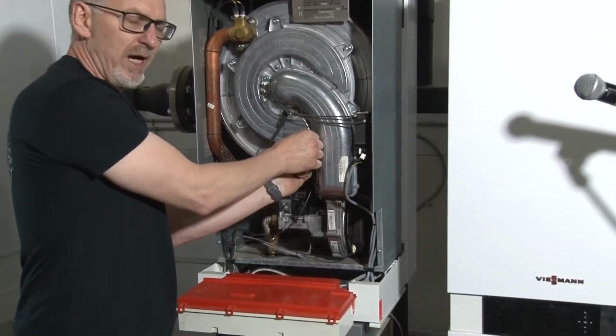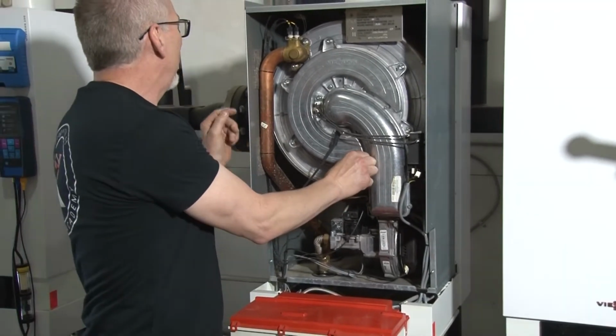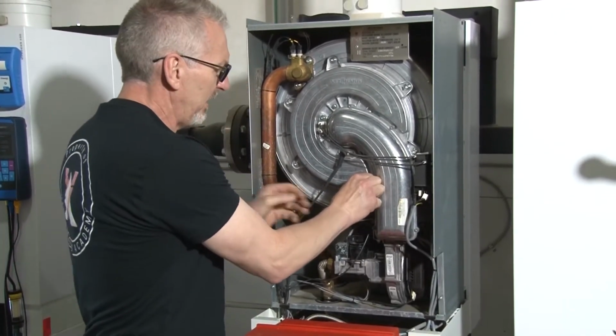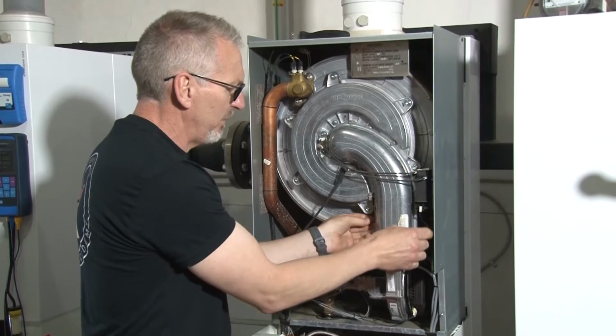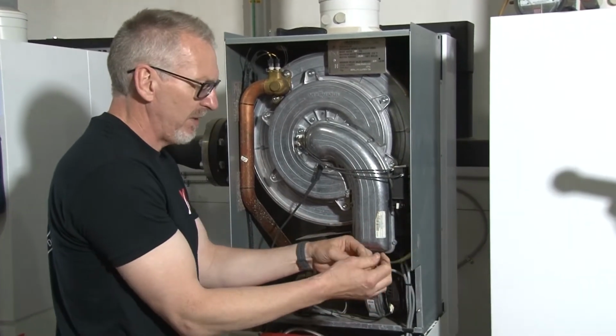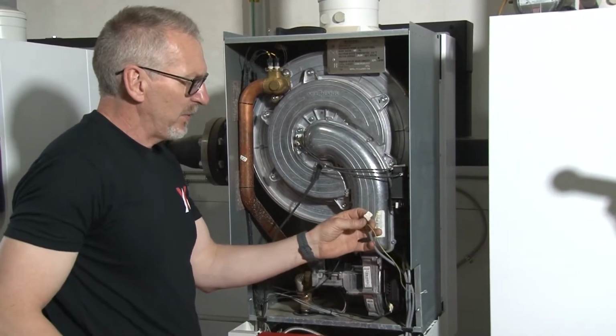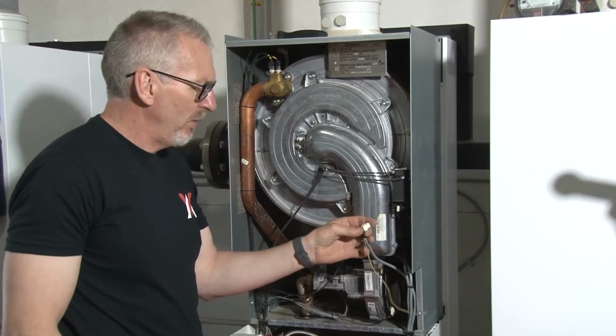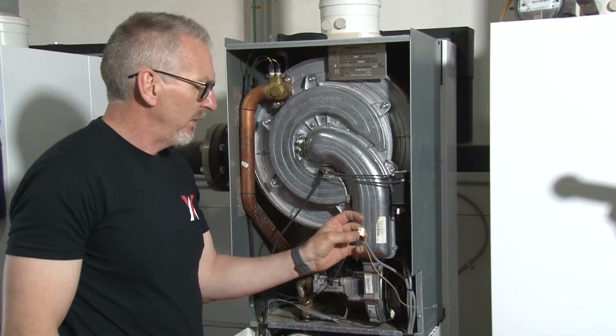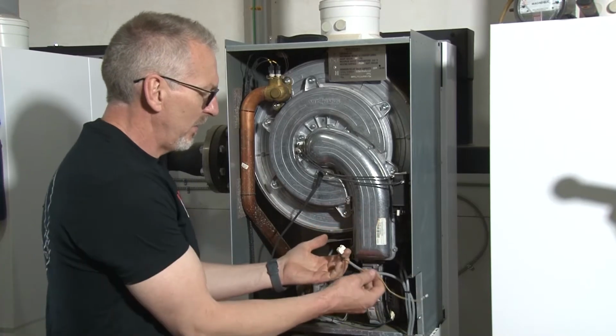We also have a burner ground. I've noticed in this boiler room they've got a nice ground directly to the manifold here as well, which really helps. You can't have too many grounds, in my opinion, so that keeps basically the resistance for flame signal very low, which allows for good continuity of your flame. So there's those two pieces down.